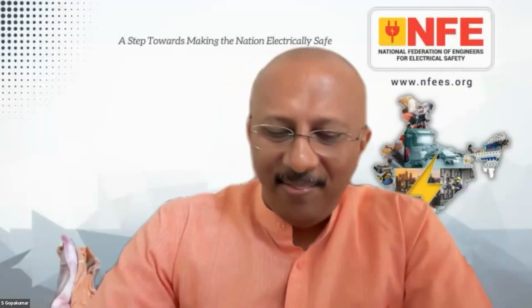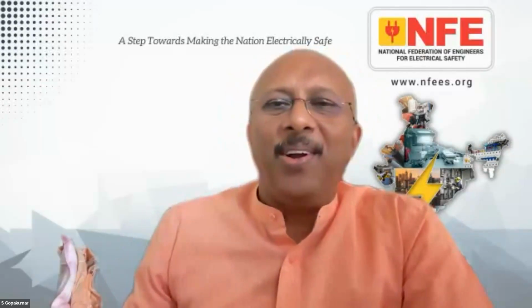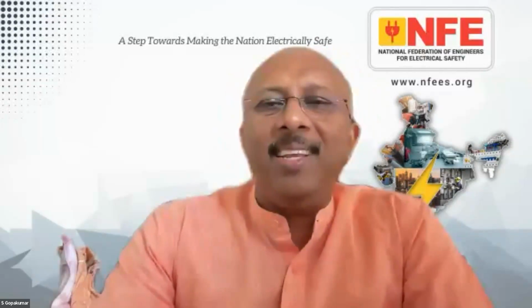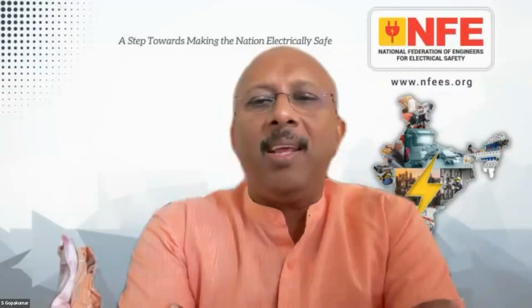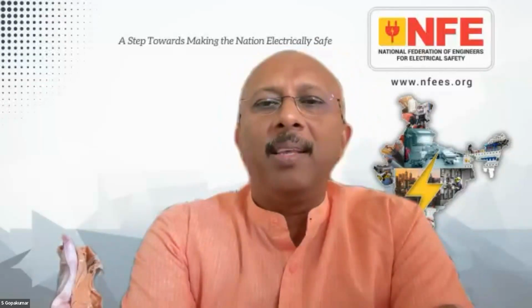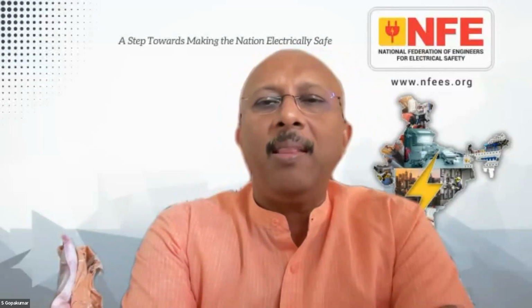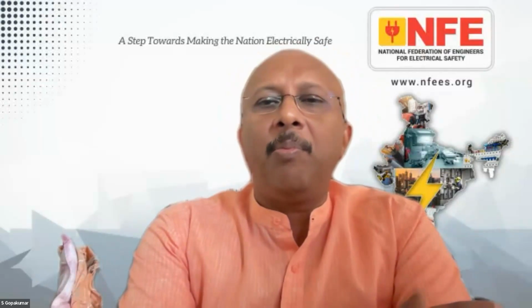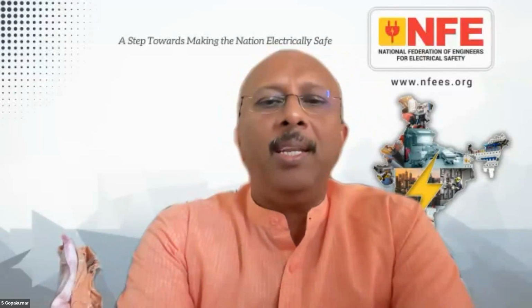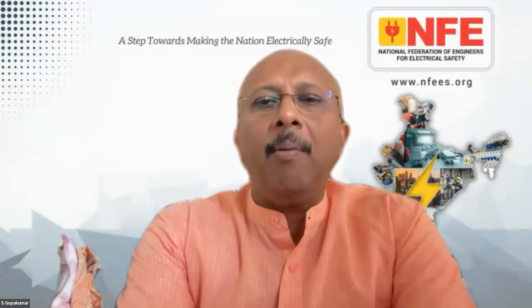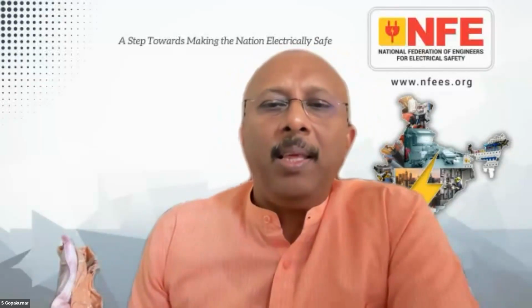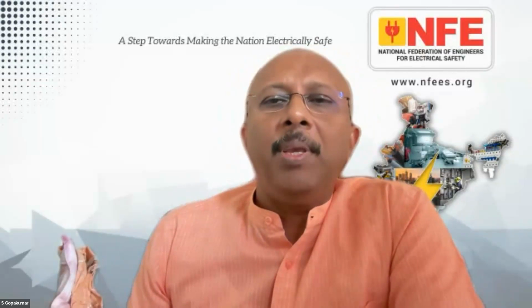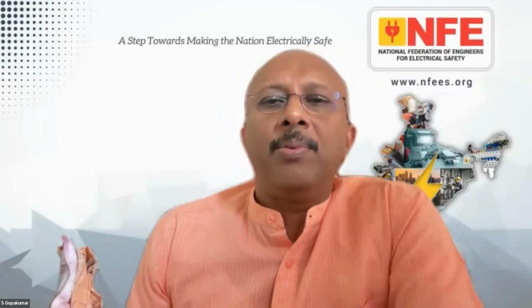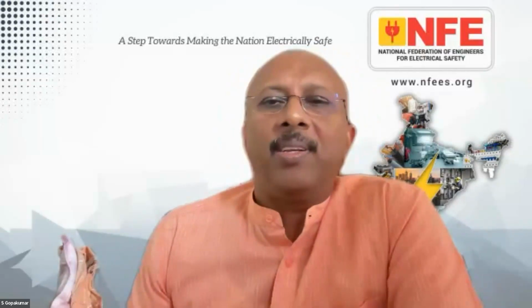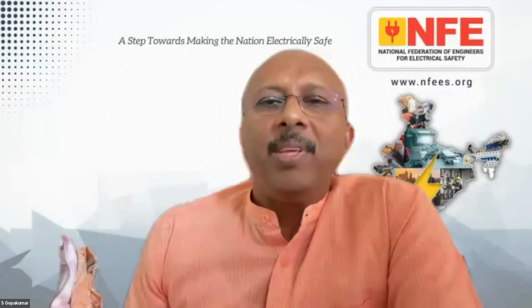But that is actually wrong, because the lift is capable of even running on an IT supply. In an IT supply, an unearthed supply, we have to handle fault protection, but that is a different case. In an IT supply, every electrical apparatus is supposed to work. In an IT supply, the neutral to earth potential can be even 230 volt. Still, these devices are supposed to work.